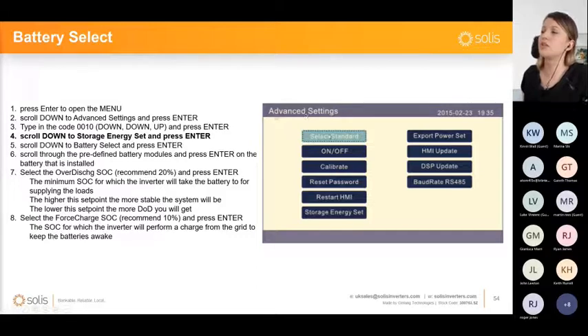Okay, so as I was saying, the password is 0010, and we're just going to enter here. So this is the advanced settings, which is the most important part of the menu. Here you have the select standard. That would be the grid standard for your country. In the UK, I think almost all the hybrids are delivered with the G99. But it's always good to double check, especially if you see some over voltage alarms on the grid side. It might be just that the standard is not right.